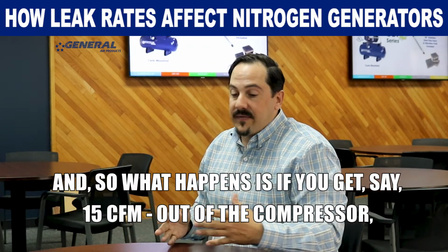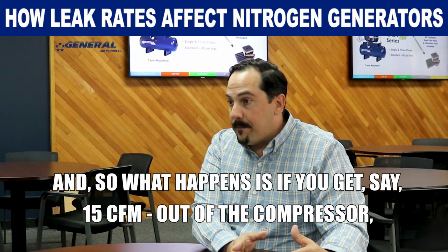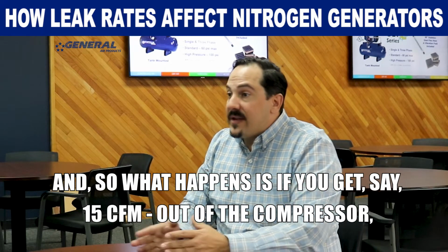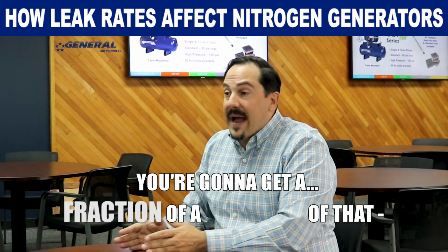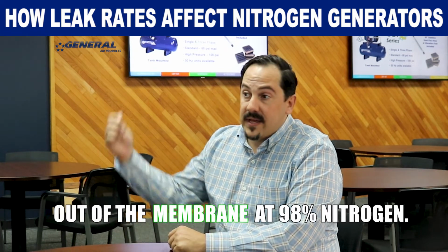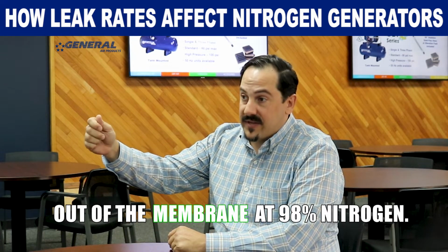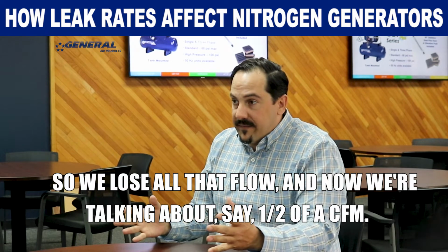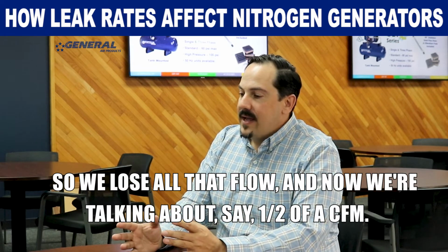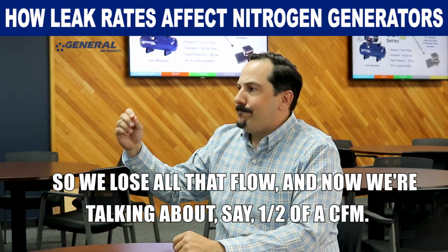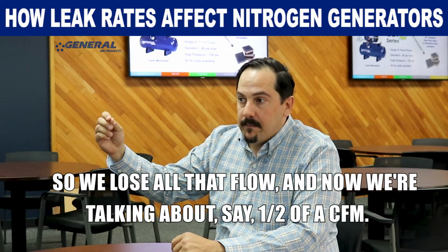So if you get, say, 15 CFM out of the compressor, you're going to get a fraction of that out of the membrane at 98% nitrogen. We lose all that flow, and now we're talking about, say, half of a CFM.